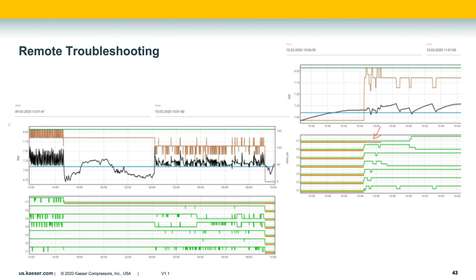And as we see here, the graphic on the left, there's actually an alarm for one of the compressors, and that compressor goes down, and for a time, pressure is severely low. Also, all the compressors seem to shut down later in the day, and that's most likely from somebody who's visiting the system, and maybe to try to figure out what's going on, they shut the whole thing down. This kind of information is great to have at your fingertips, but again, in that particular case, we'd be reacting to the system.